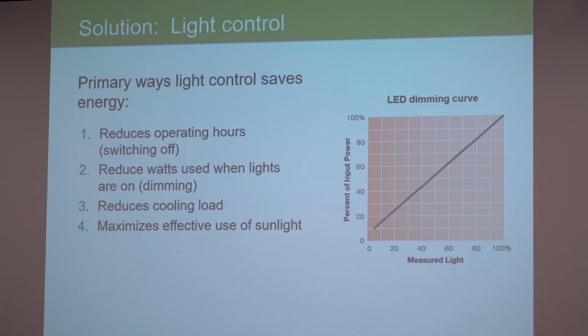Secondly, when the lights are on, light control saves energy by reducing the wattage, or the power, of the lighting while the lights are on. In other words, dimming lights saves energy. In fact, the graph you see here is an LED dimming curve, and it's basically linear. The lower the light level, the lower the energy usage. And it's the same looking graph for fluorescent, incandescent, and halogen.